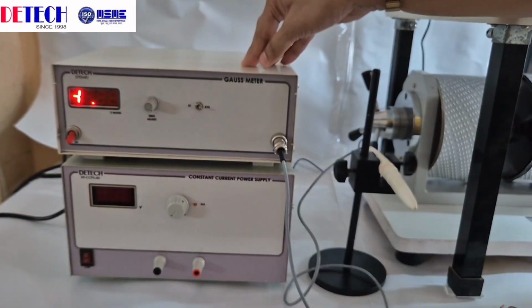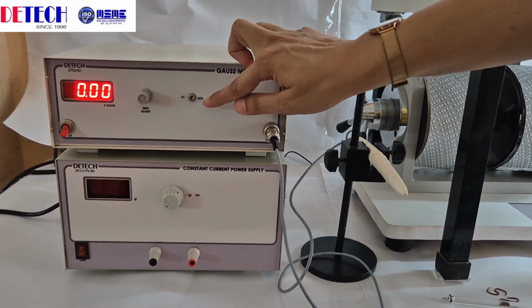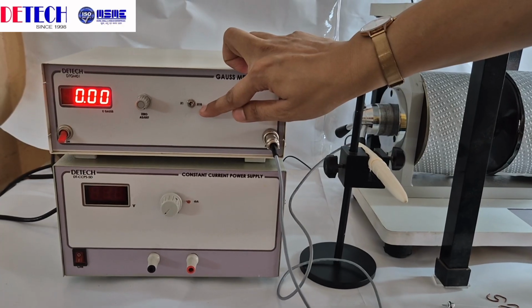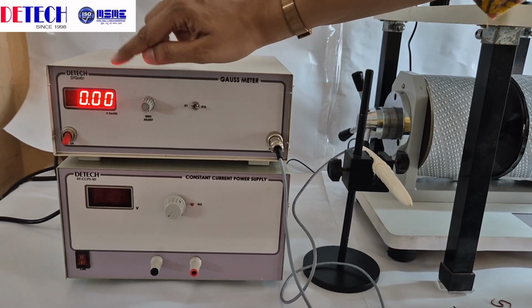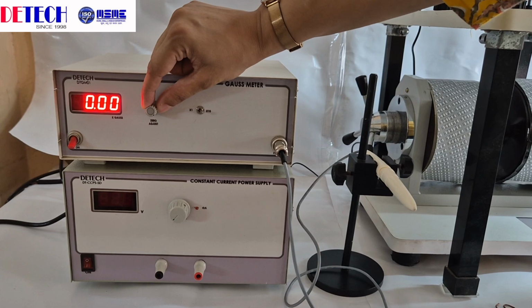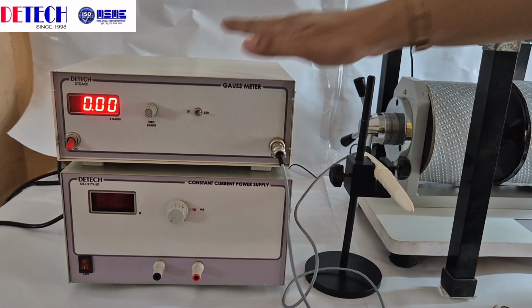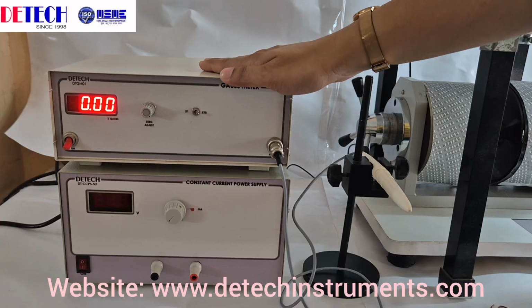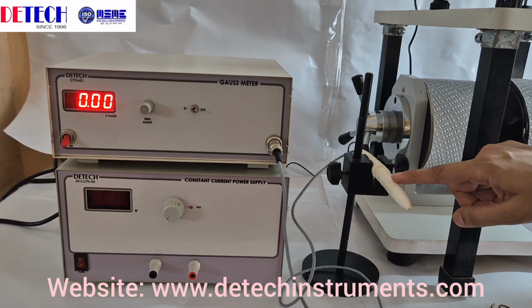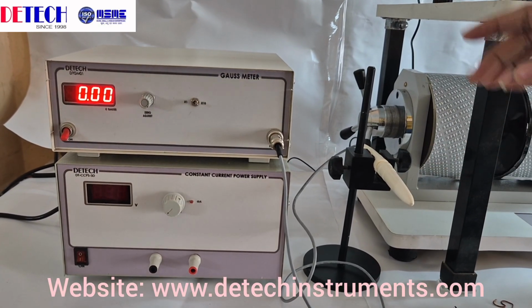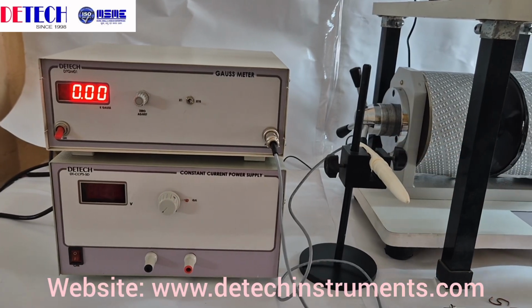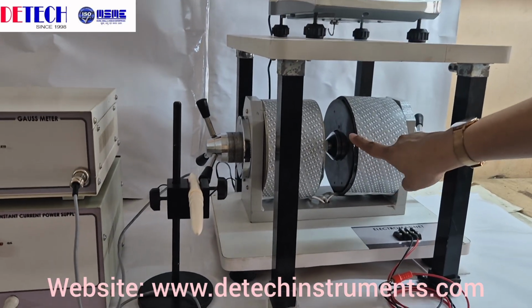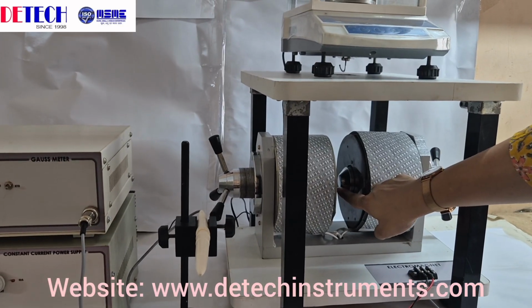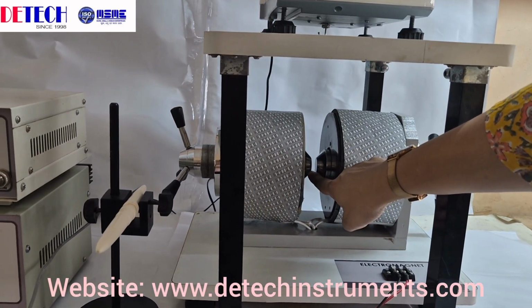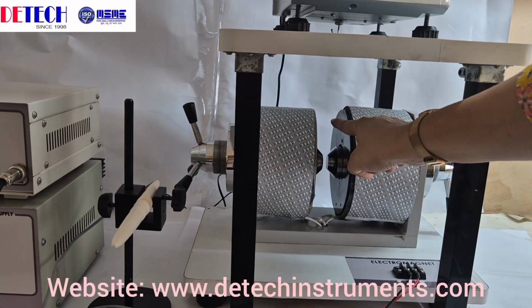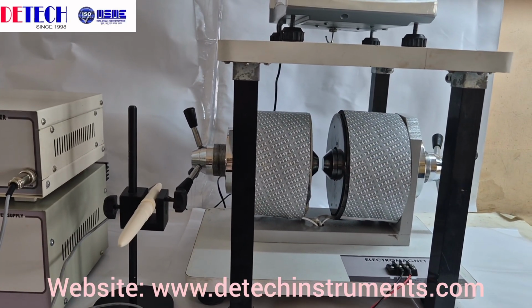Let us switch on the digital gauss meter. So right now it is in this range, which is a multiplied by 10 range, and it is showing 0. If it is not showing 0, you can adjust the 0 using this knob. Make sure that the electromagnet is not on when you're adjusting the gauss meter, and this is covered with the protective sheath. So once it's 0, we will set this in between the electromagnet over here. As you can see, there is a gap of around 10 millimeter between the two poles of the electromagnet. We will set the probe over there and then we will measure the field strength.